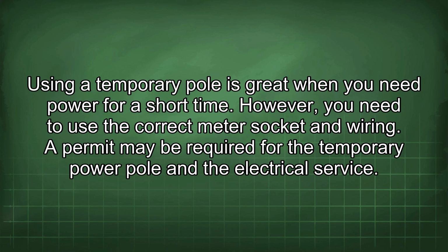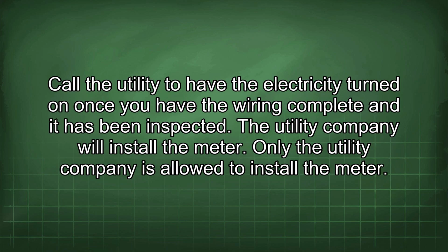Using a temporary pole is great when you need power for a short time. However, you need to use the correct meter socket and wiring. A permit may be required for the temporary power pole and the electrical service. Call the utility to have the electricity turned on once you have the wiring complete and it has been inspected. The utility company will install the meter. Only the utility company is allowed to install the meter.